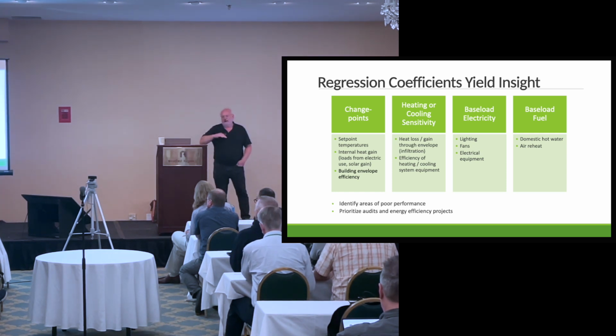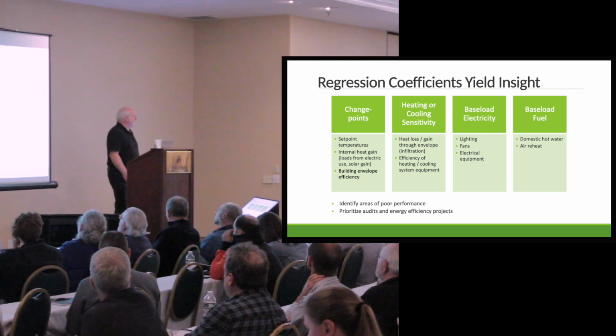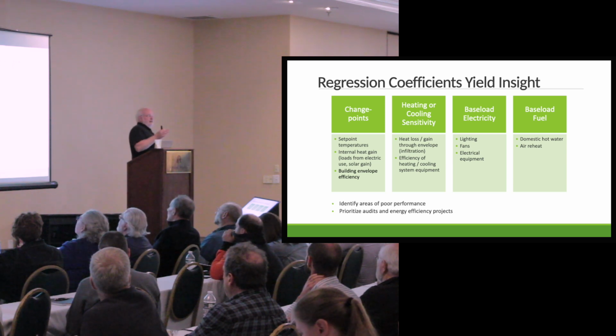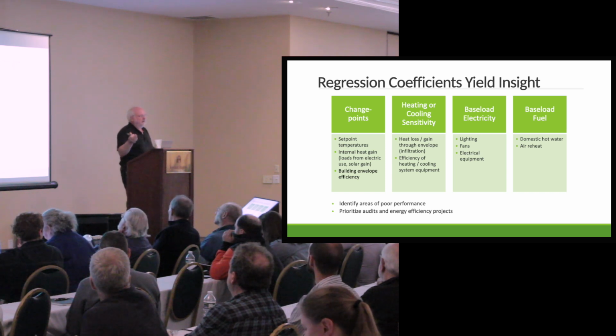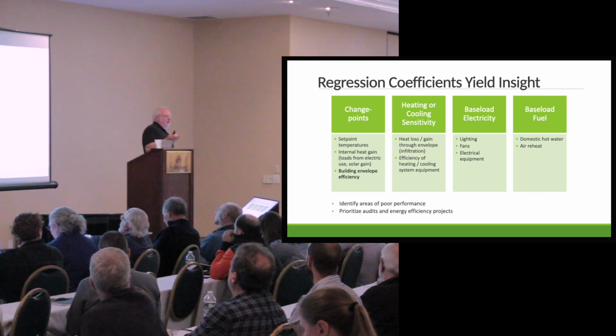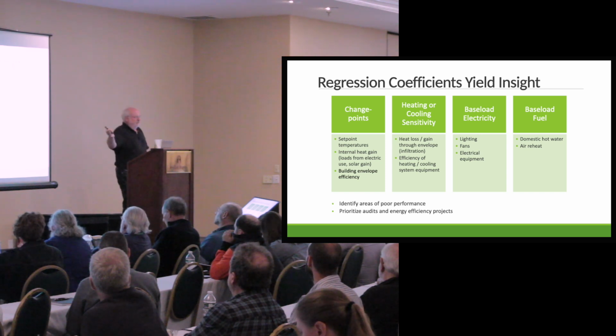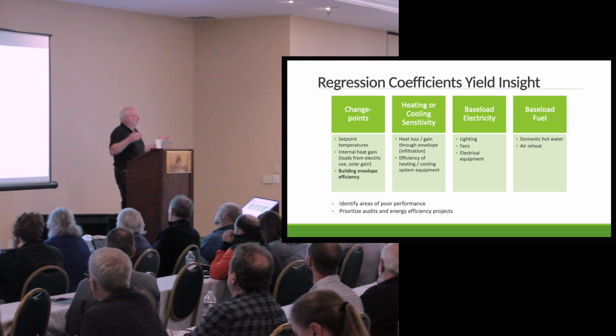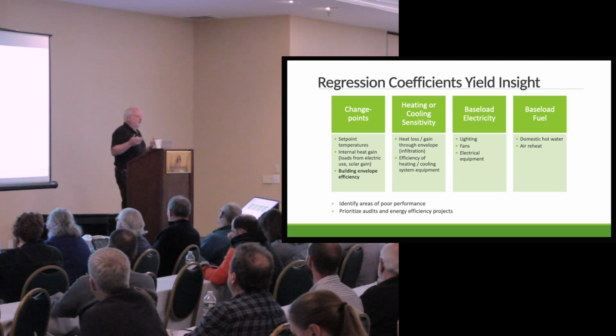These coefficients — how steep the slope is, where the baseline is, and where the change point is — can all tell you things about the buildings: how much base load you've got, how fast energy consumption rises as outside air temperature changes, and where the change point is. For example, on a heating model you'd want to see the change point around 65 or 63 degrees. If you see that heating model changing at 75 degrees, well, why are you heating the building when it's 75 outside? Maybe something's wrong with how the building's operating.